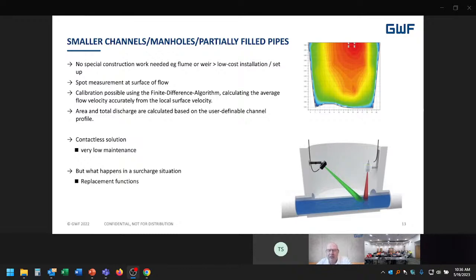Now, there is a challenge that if, say, you had a surcharge event, maybe an inflow causing the sewer to go up the manhole, the actual level of the water to go up and beyond, say, the radar velocity sensor, that could then cause a problem, because if it's covered in rags, it might not measure. If the level sensor is located further up within the manhole, that allows us to maybe avoid the issue of the sensor getting covered in rags and otherwise.